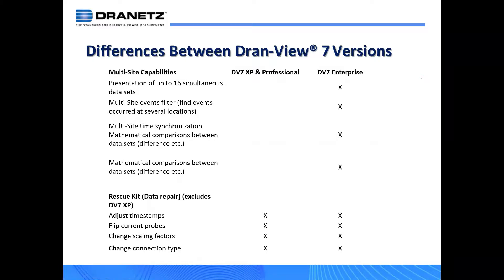Dran-View Enterprise offers something called multi-site, which is very powerful for large or medium-to-large monitoring projects. If you're doing an acceptance test or troubleshooting with multiple instruments, Dran-View Pro lets you look at all that data but as individual instances — they don't interact together. Dran-View Enterprise can treat up to 16 simultaneous data sets as one, so you can compare voltage on instrument one to instrument two to instrument three on the same screen and see how a power quality event ripples through your facility.